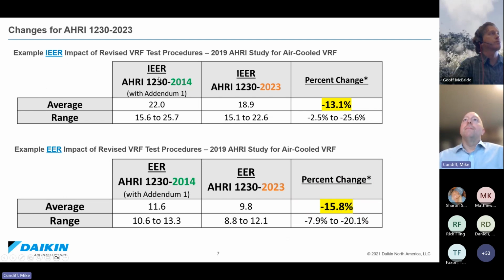So, example IEER impact for these test procedures. What this is showing is the average percent change based on this new, more stringent test procedure. The average percent change is all the numbers are dropping by about 13%. The range on that is 2.5% for some manufacturers, up to 25.6% for others. So you're going to see some differences there in what the energy efficiency numbers are.